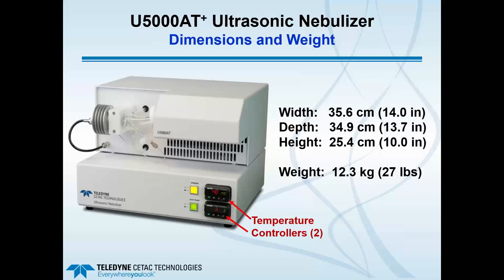A front view of the base ultrasonic nebulizer — this is the U5000 AT+, which has been widely used for many years for aqueous samples, particularly for things like drinking water and wastewater. You can see on the right-hand side the width, depth, and height dimensions. It's very much a benchtop-style unit that can be placed next to the ICP or on a laboratory cart. One important detail is the two temperature controllers in the lower right: the top one is for the heater, and the bottom one is for the cooler, which cools the condenser.